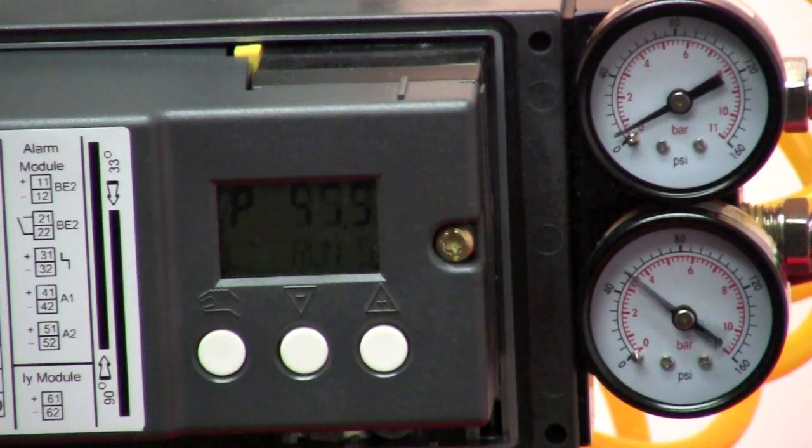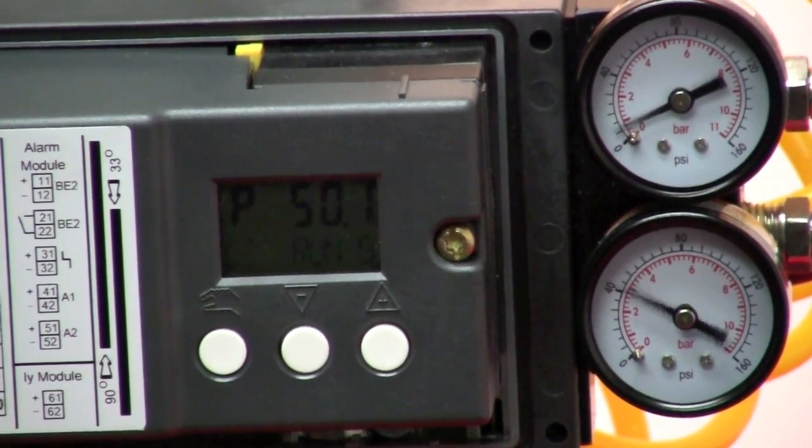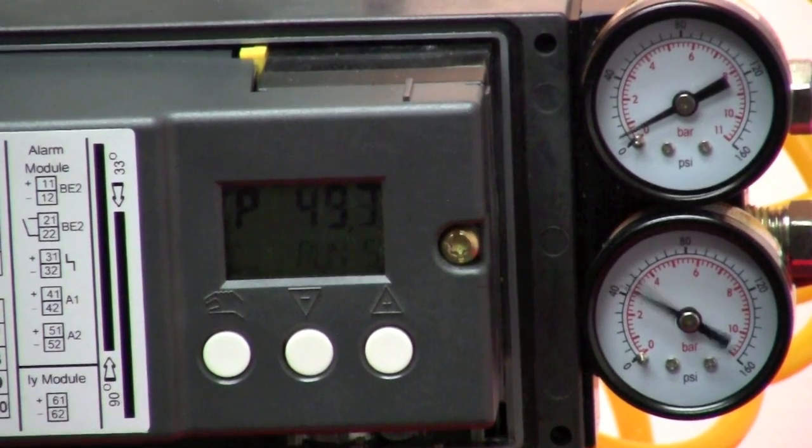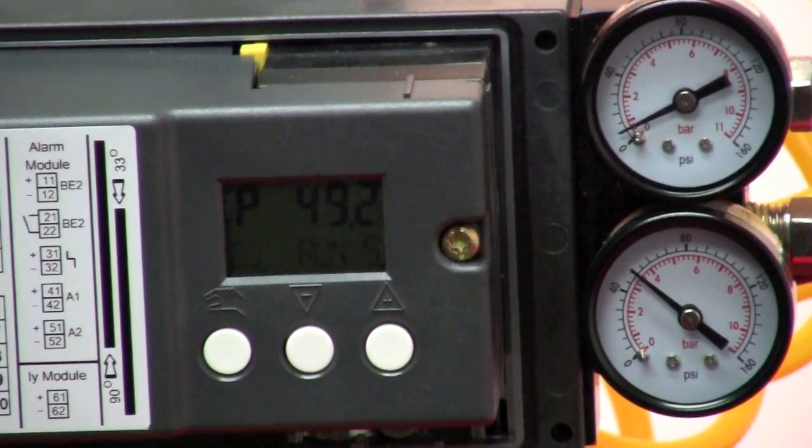And run 5 optimizes the transient responses. All of these parameters are tracked over time during normal positioner operation and changes in these parameters due to valve friction or packing degradation or seat degradation can be alarmed on using our diagnostic software or an asset management system.